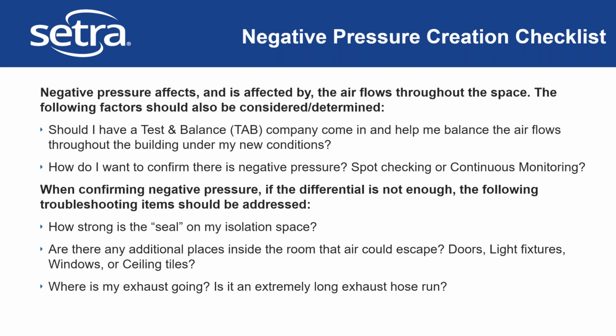And then lastly, as you think about a portable unit like the Setra AirWatch, that exhaust hose run, if you're trying to extend that beyond 15 to 20 feet, then you should also think through, okay, what does that do to the ability of my unit to exhaust the air at a certain flow rate? So again, it's easy to roll a portable unit into a space, plug it in, and set up a removable exhaust. But you do want to think through the full effects of that on your building, and what that would mean for your entire space.